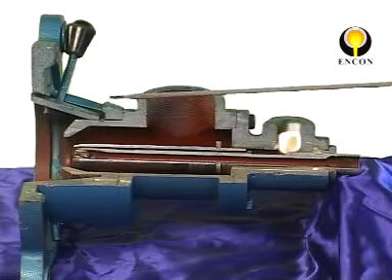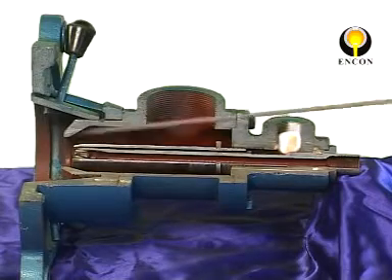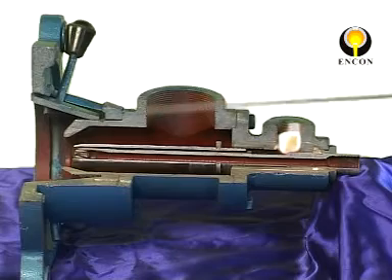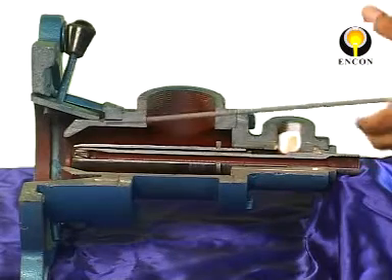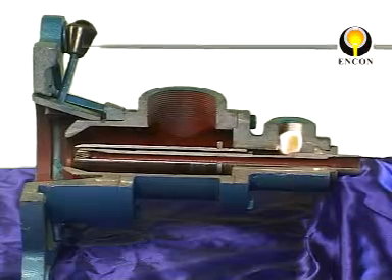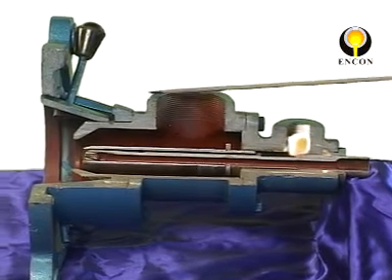So a film of oil, a hollow cylinder film of oil is formed through two layers of air and because of this concept, you do not need to have excess air given to the burner to complete the combustion and that's the reason this burner saves fuel.